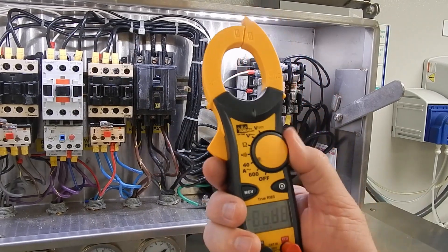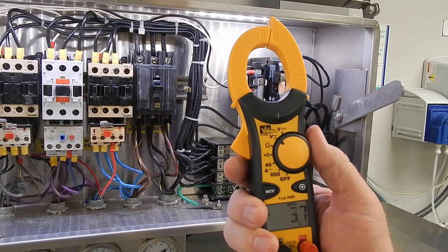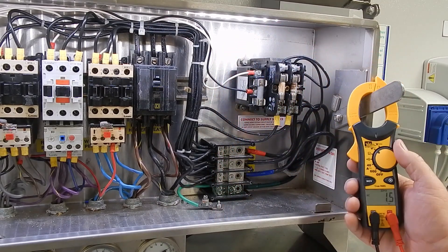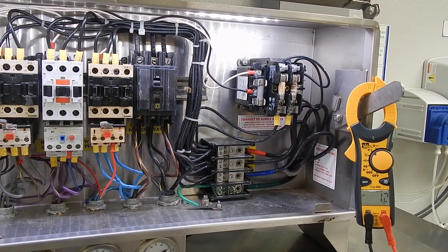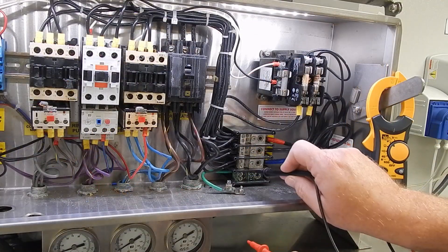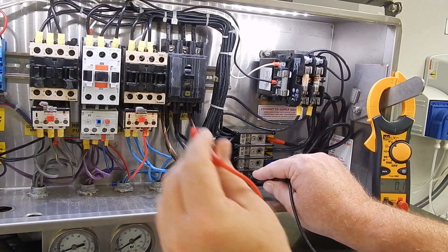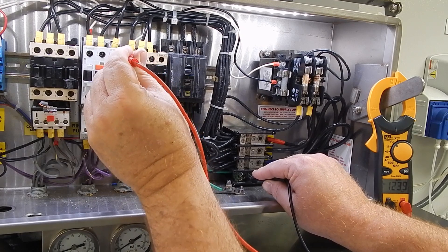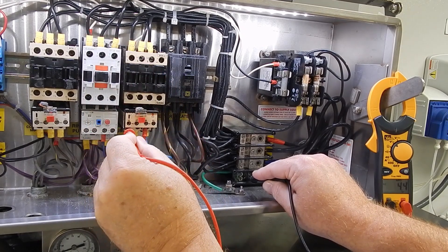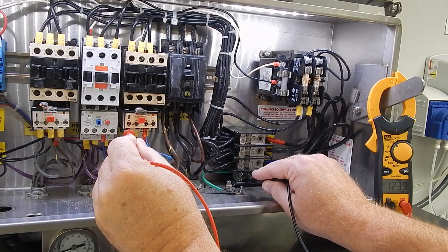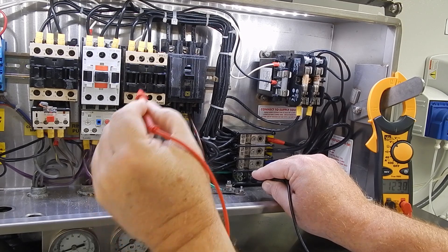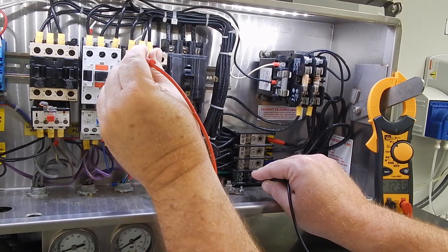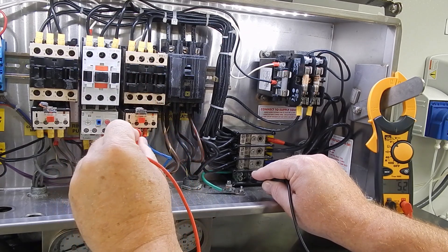Let's take a look at how we are testing this on the machine. Again, we are setting our multimeter to AC voltage. One meter lead goes to ground, and we go to the top side of the wash motor contactor on L1, and we test the output side of the contactor on L1. We are verifying voltage coming through the contactor.